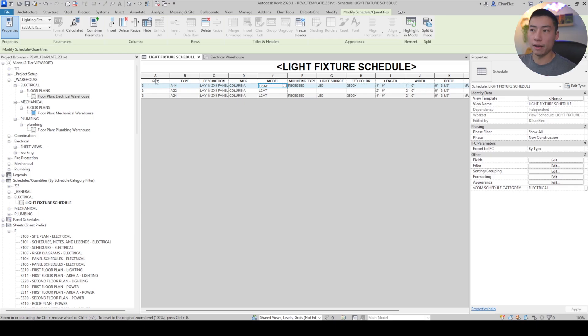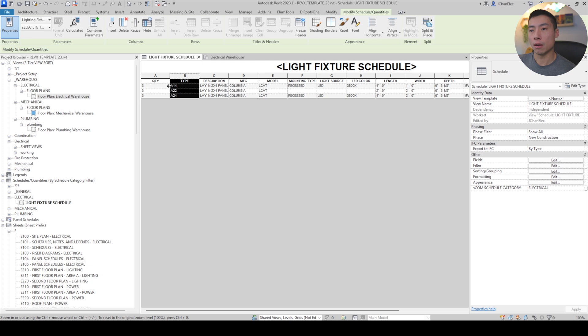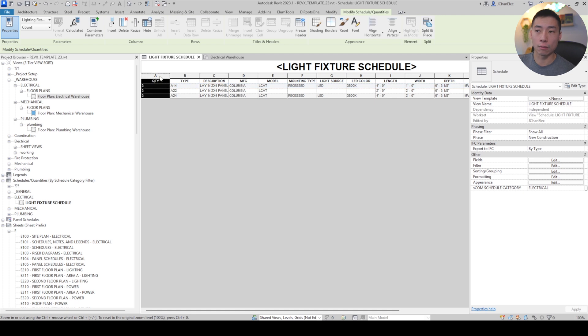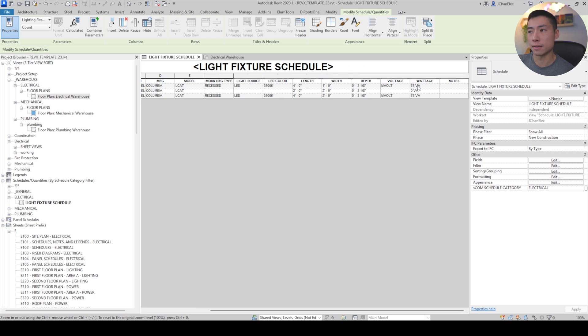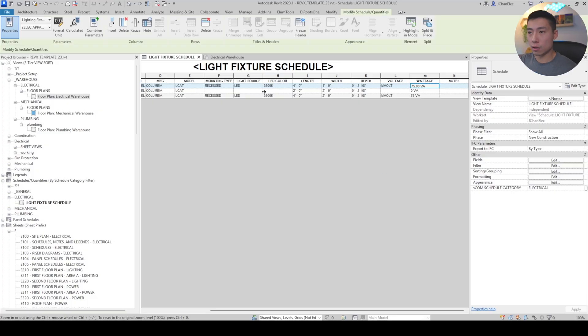In this project I have a light fixture schedule set up already, and this is basically the end goal. We want a smart schedule that can pull in all the different types of light fixtures and describe what each one is - the manufacturer, all that good stuff. Because this is a smart schedule, you can add a column for quantity to count how many fixtures are in your project. There are other properties you can put in here, such as the load - you can tell a fixture it has 75 VA of load, and when you circuit it in Revit it pushes this load into the panel schedule. All of this is very intertwined.